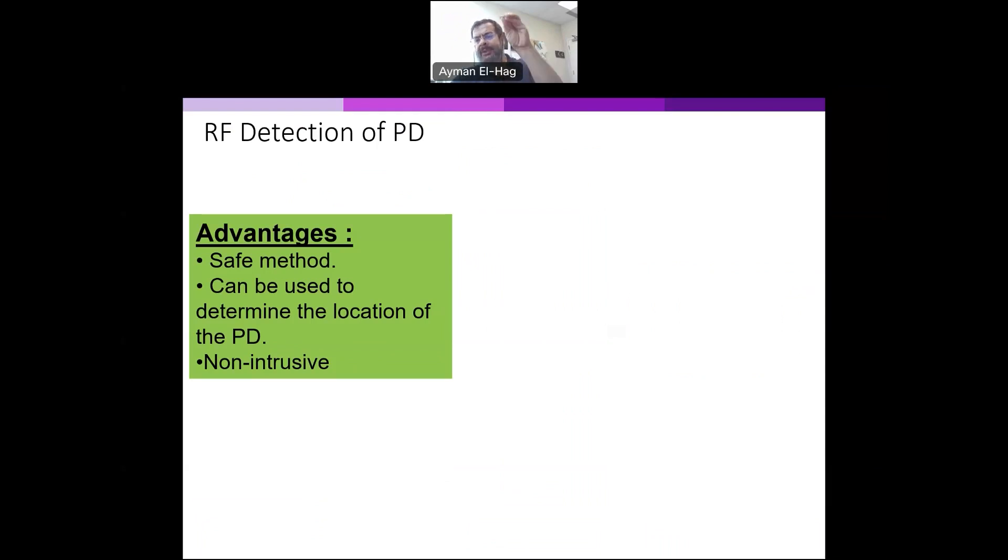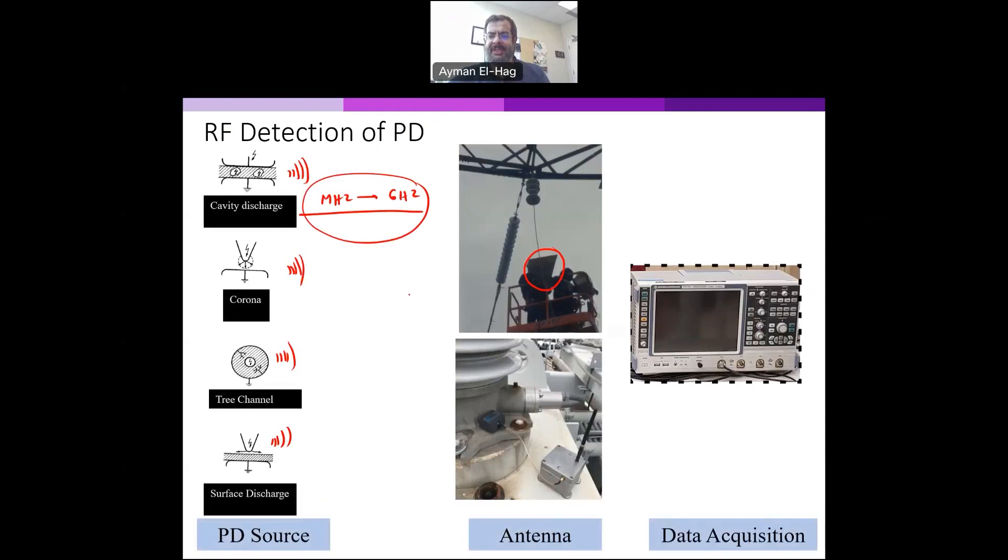Except if we have to put it inside the device, as you can see here. This is the antenna used to detect partial discharge for outdoor insulators. That is completely non-intrusive. But if I have to insert the antenna inside the bushing here or inside the GIS system, it is a sort of intrusive test.